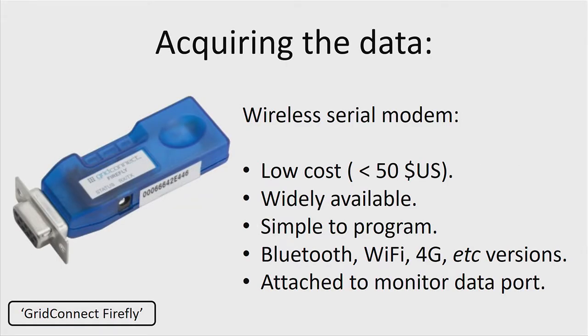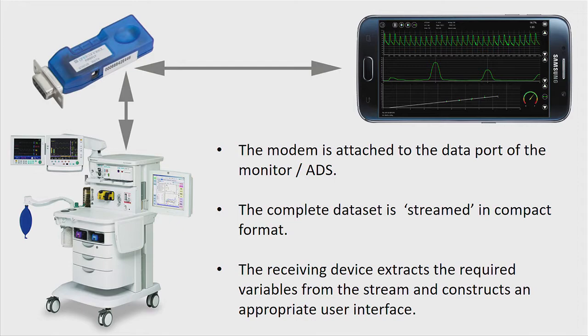How do we get the data? You use what are called wireless serial modems. The cheapest of these costs about US$50. They're widely available, simple to program, and come in all sorts of flavors — from Bluetooth through Wi-Fi through 4G. You simply attach them to the monitor's data port. In this example, I've attached a Bluetooth serial modem to the anesthesia machine, which is streaming data to a mobile phone that selects variables to plot and creates a user interface. In this particular example, it's also performing a fast Fourier transform in real time.